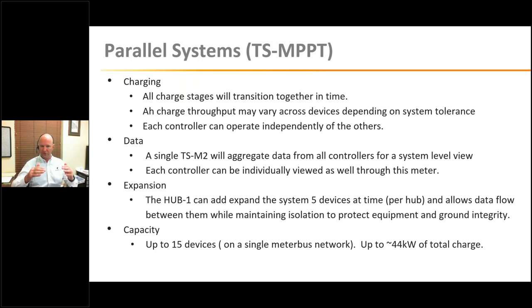So they'll go through your bulk, your absorption stage when it reaches full, and then all gradually transition to float. They won't always do it at the same time, but that's fine because the battery doesn't always need all the current of all controllers. You'll have several of them slowly transition into those stages over time, and that's usually fine because you're limiting current anyway at that point in absorption or float. The battery is pretty much finished with its charge.